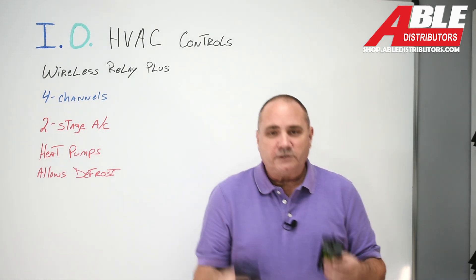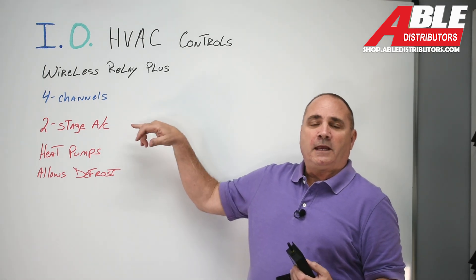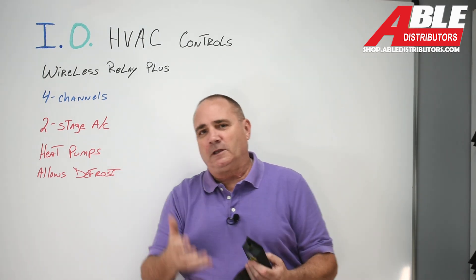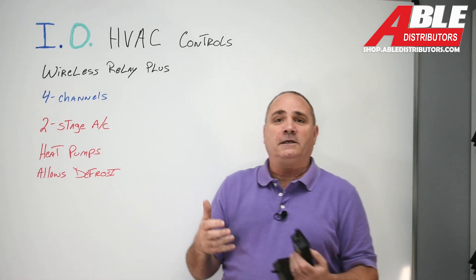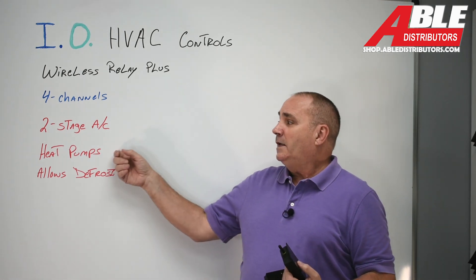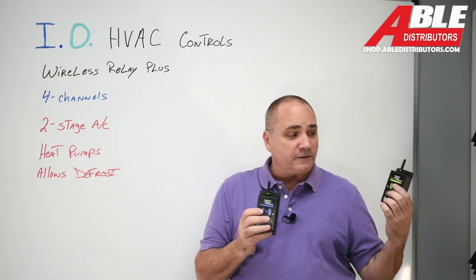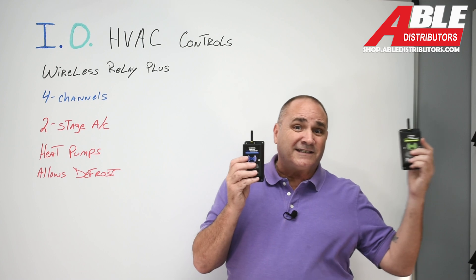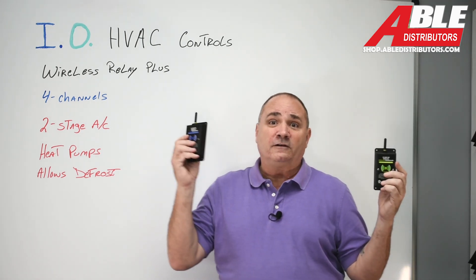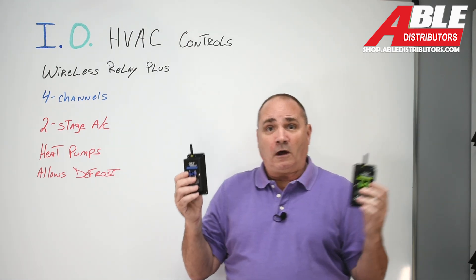So why would somebody need this? Two-stage AC — you can't really time this thing out. You could just jump it into high, which means you spent money on a two-stage AC and you're not using it to its full capacity. Heat pumps — we need to send more signals out, and then we need a signal from the heat pump coming back in when it goes into defrost to fire up a little bit of heat.